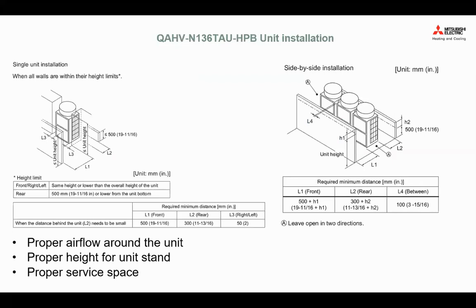So here are a couple more examples on the QAHV on the installation side. You can see if it's installed by itself, again, the installation space, or the minimum required service space, is very small. So it means it can be installed in a very small space, right? And then you can also stack them, or join them together in a modular combination. So you can have side-by-side installation and consider one entire system as up to 16 units all installed together.